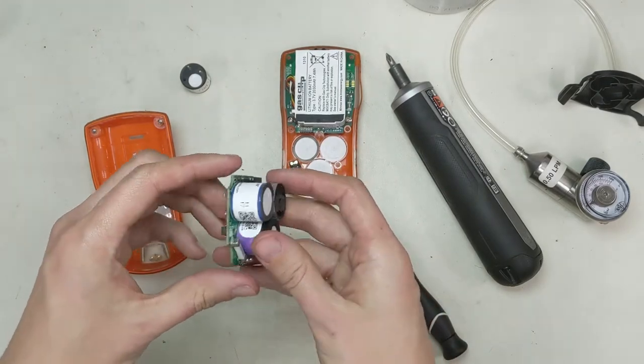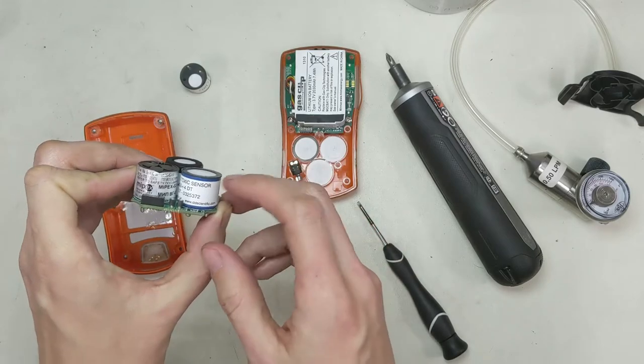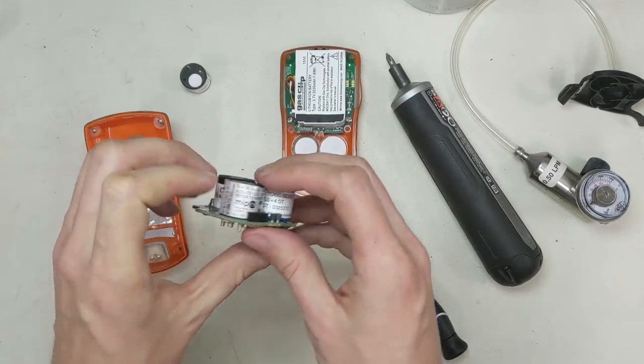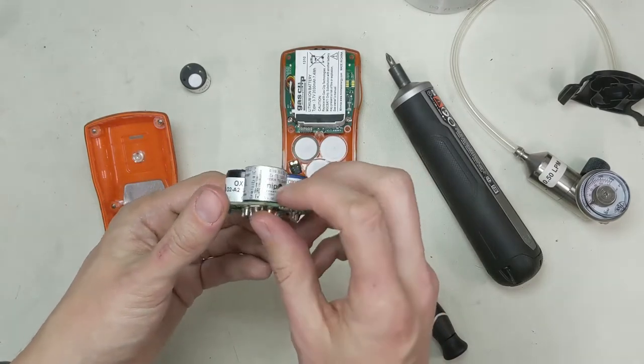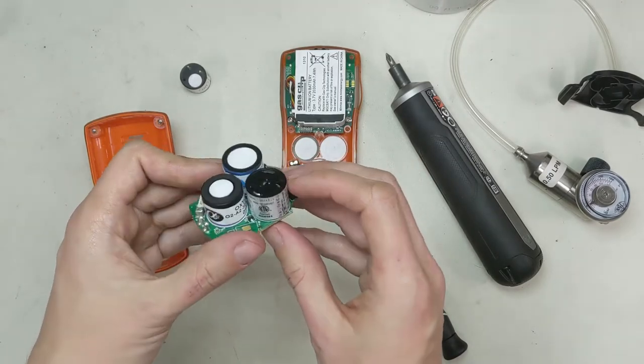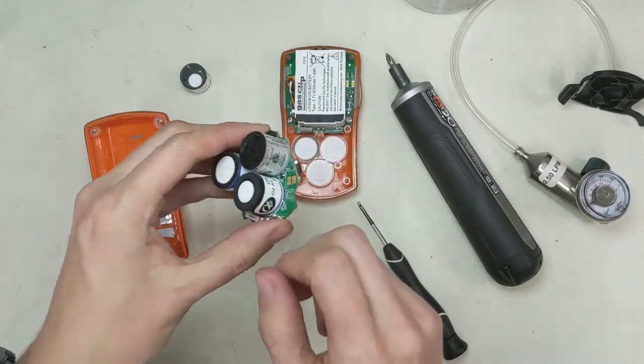Alright, here's our sensors here. So this right here is our COSH sensor. So this has a CO and an H2S on it. Over here, this is the infrared sensor. This is kind of what GasClip is known for, is this infrared LEL sensor. It's a pretty cool one. And now here's our oxygen sensor that's dead.